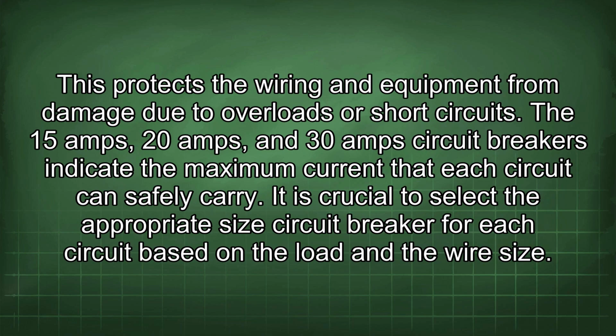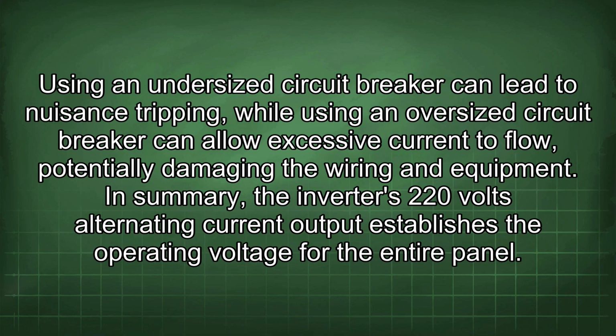This protects the wiring and equipment from damage due to overloads or short circuits. The 15 amps, 20 amps, and 30 amp circuit breakers indicate the maximum current that each circuit can safely carry. It is crucial to select the appropriate size circuit breaker for each circuit based on the load and the wire size. Using an undersized circuit breaker can lead to nuisance tripping, while using an oversized circuit breaker can allow excessive current to flow, potentially damaging the wiring and equipment.